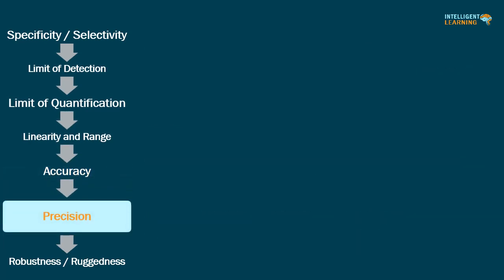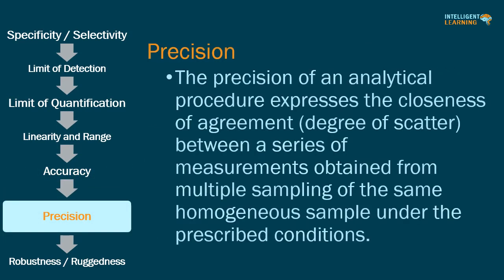The precision of an analytical procedure expresses the closeness of agreement — the degree of scatter — between a series of measurements obtained from multiple sampling of the same homogeneous sample under prescribed conditions. Precision may be considered at three levels: repeatability, intermediate precision, and reproducibility.